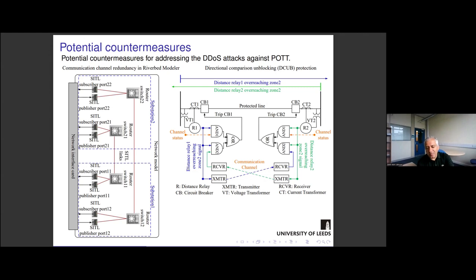But there are 2 problems with these 2. Basically, these 2 countermeasures are the measures that have been classically used in power systems for communication network failure, not for cyber attacks against the communication network. So as we can see, again, if an attacker attacks both communication channels that we consider here as a redundant communication channel, the same thing will happen. And also, if the attacker used a false data injection attack or a supply chain attack, these scenarios are not useful anymore because they are not able to detect or address the attack that we have.